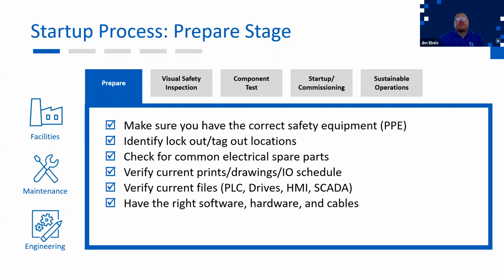You want to verify you have the current files, whether it be your PLC, your variable frequency drive, HMI, SCADA, motion and vision inspection, and robotics, making sure you have the latest version of the programs for that equipment, along with making sure you have the latest version of the programming software, or at minimum the latest version needed to run those updated programs, as well as any hardware, download cables to load the programs and connect.